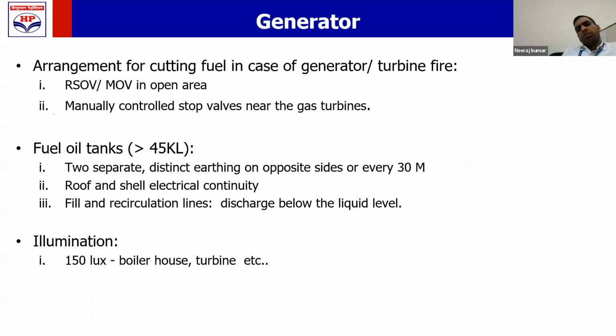So in case there's a fire in the generator, the first thing you should be able to do is cut the fuel supply to the generator. How can it be achieved? For that, you should have one ROSOV or MOV on the fuel supply line in an open area, not near the generator. Provide a remote control solenoid operated valve or a motor operated valve in an open area on the fuel supply line of the generator. This is a mandatory requirement.